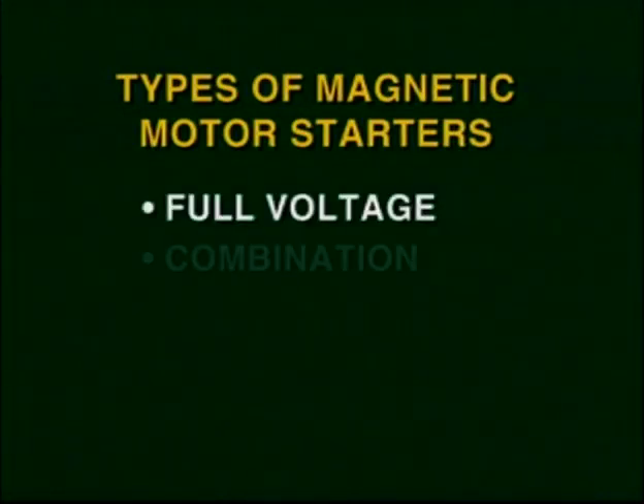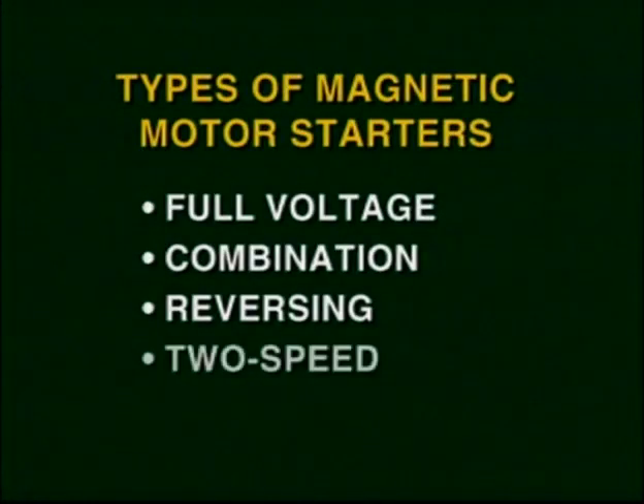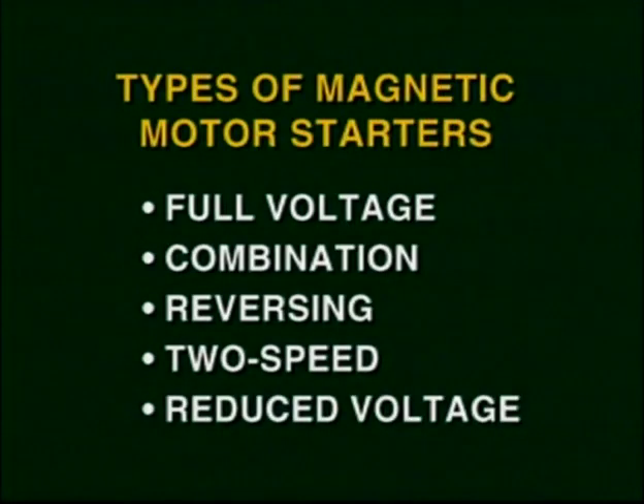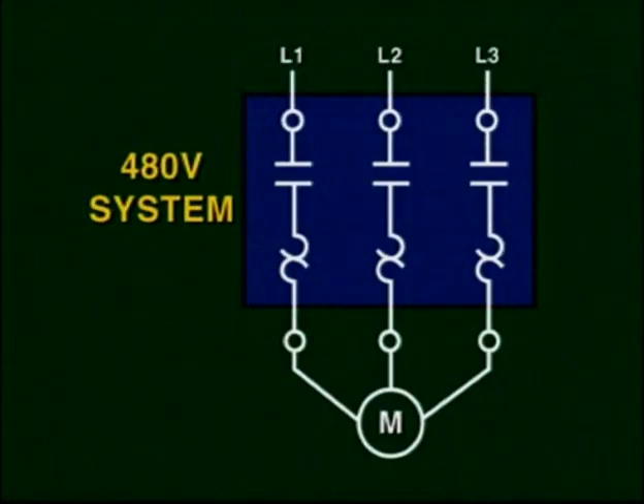There are several types of magnetic motor starters, which are the full voltage, the combination starter, the reversing starter, the two-speed starter, and the reduced voltage starter. The full voltage starter is perhaps the most commonly used in industry. This motor starter is also called across the line because it switches the full voltage to the motor once the starter coil is energized. In the same cabinet or enclosure, combination starters provide a magnetic starter combined with a disconnect switch, which can be fused or non-fused. This arrangement, provided by manufacturers, allows for a quick and convenient installation of a motor control in a single enclosure. Start-stop push buttons are also available in the front of the cabinet.